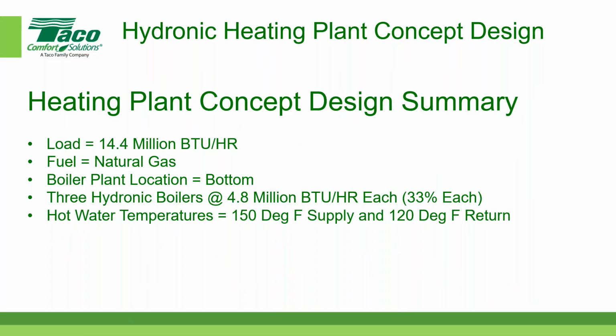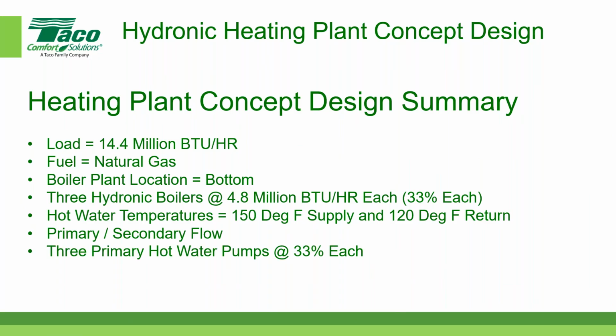The hot water temperature in this case was 150, with a return water temperature of 120, so it's a 30-degree delta T. Because the return temperature is below 130 degrees, this concept design could be a potential candidate for modulating condensing boilers. So that's something to take into consideration. My concept design is not based on condensing boilers, but it could be because you have a low enough return water temperature. I decided on a primary secondary flow for the configuration of the piping system.